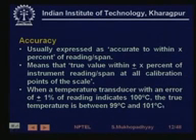So what it means is that if a reading is 100 and it has plus minus 1% of, let's say, span accuracy, then the true temperature will be between 99 and 101 degree centigrade.